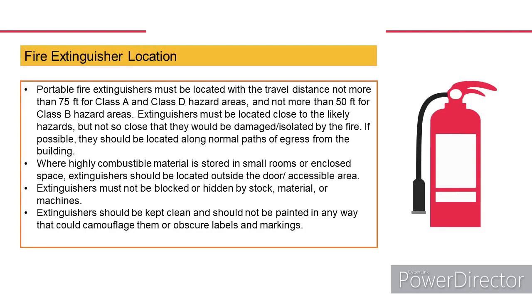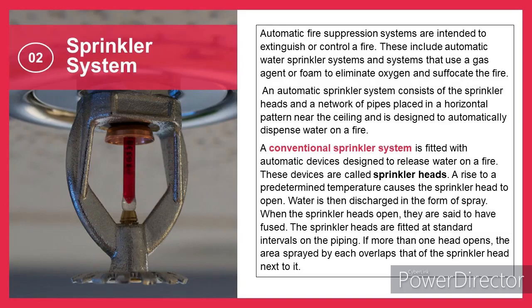Portable fire extinguishers must be located with the travel distance not more than 75 feet for Class A and Class D hazard areas, and not more than 50 feet for Class B hazard areas. Extinguishers should be located outside the door/accessible area. Extinguishers must not be blocked or hidden by stock, material, or machines. They should be kept clean and should not be painted in any way that could camouflage them or obscure labels and markings. Now we move on to the next system, the sprinkler system.